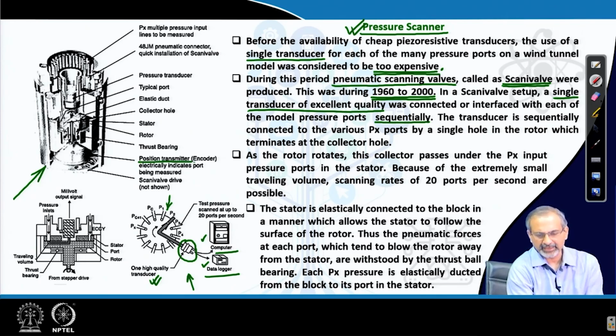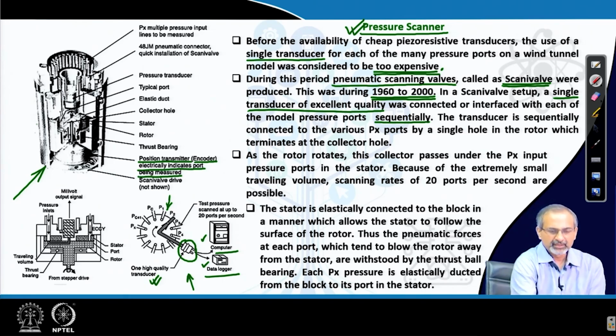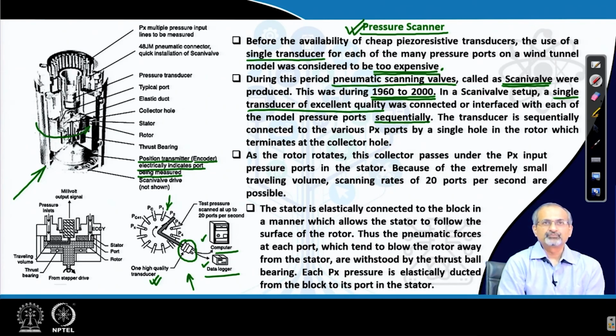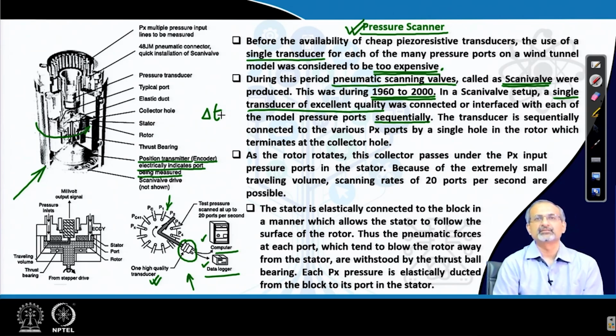The position transmitter or encoder electrically indicates the port that is being measured currently, because from time to time there would be a rotation and thereby only one particular pressure port at a time will be interfaced with the pressure transducer. Remember again that since we have only one pressure transducer in this setup, this indexing will be required. This interfacing with different pressure ports one at a time sequentially would be required. Let us say you have 100 ports on the model, then in a given time you would move from port 1 to port 2 to port 3, complete up to 100 and then again come back to port 1, and over a short duration delta t you try to record the pressure coming from each port through that pressure transducer.